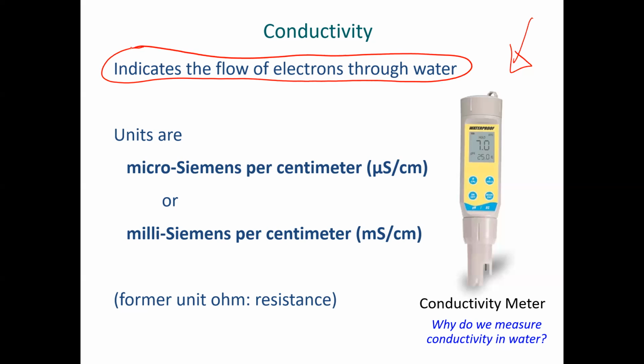So generally, conductivity is directly related to total dissolved solids because most of those total dissolved solids are ions. So there's generally a very correlational relationship. And so conductivity you measure very quickly, use the probe, and then it automatically gives you an idea of what the total dissolved solids is.